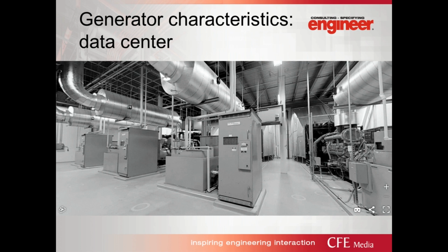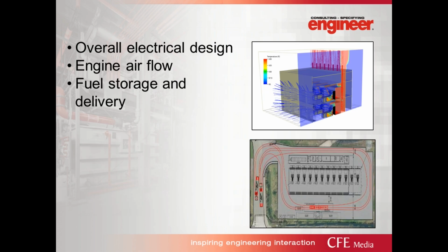There's flexibility and freedom in design, and that opens up a lot of options and possibilities for the designer and the owner. So three things I just wanted to touch on today were overall electrical design with the final build in mind, engine airflow and how critical it is to consider that. People think that generators are all electrical. They're actually more mechanical in many ways. So mechanical engineering is also very critical to the design of a good generator system. And then fuel storage and delivery as well.